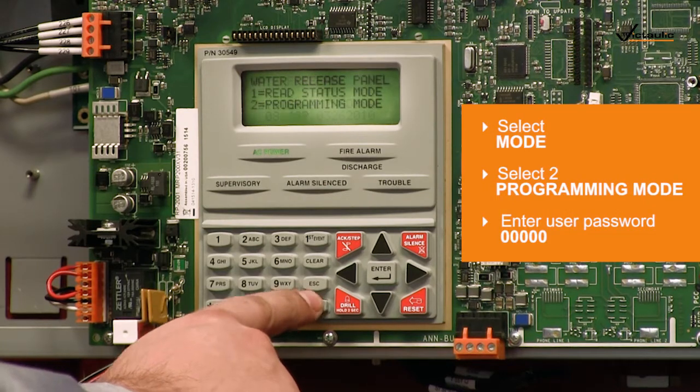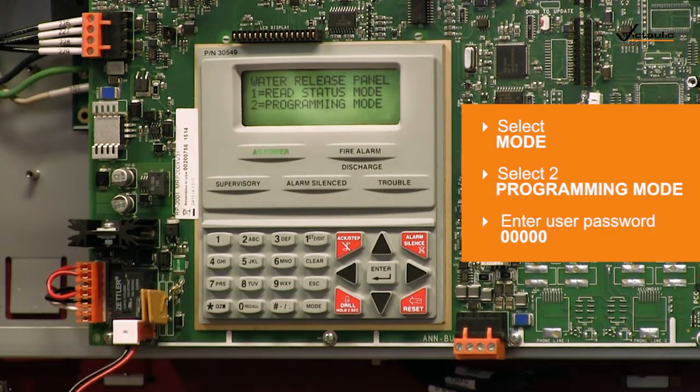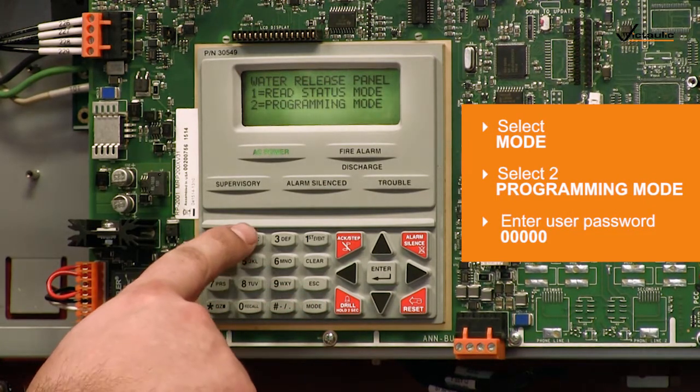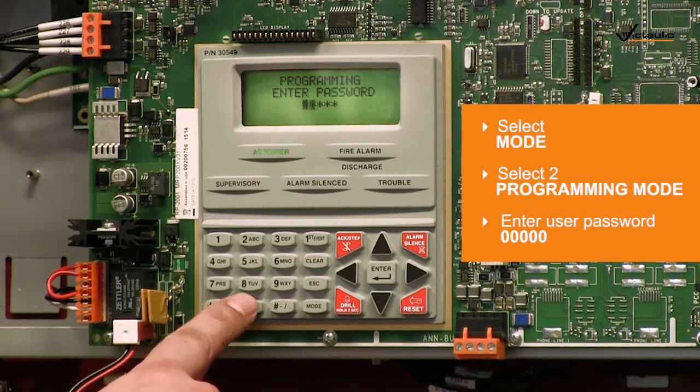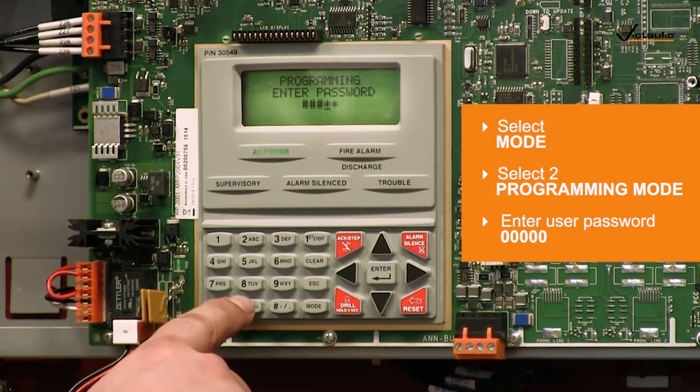To adjust settings, select Mode on the key panel. Next, select 2 for programming mode. Enter the 5-digit user password. Factory default is five zeros. The trouble light on the key panel will flash red when the password is entered correctly.